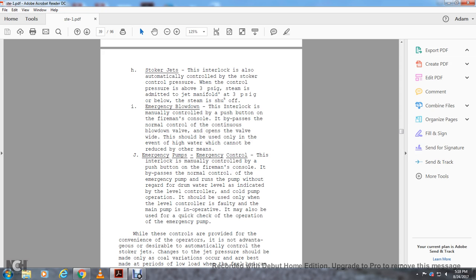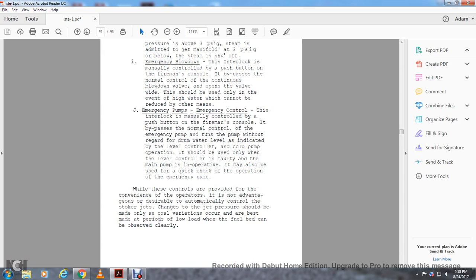Cold pump operation should be used only when the level controller is faulty and when the main pump is not operative. They may also be used for a quick check of the operation of the emergency pump. While these controls are provided for the convenience of the operator, they are not advantageous to the desirable automatic control of the stoker jets.